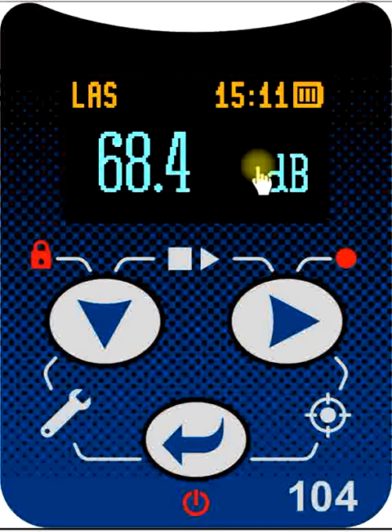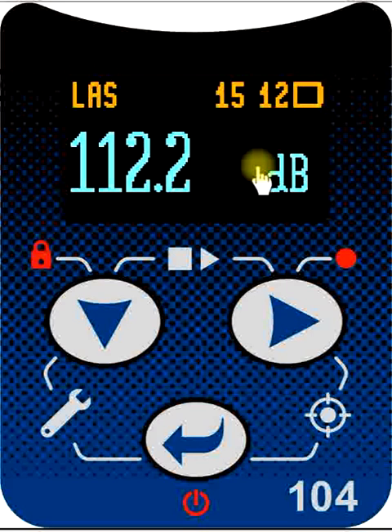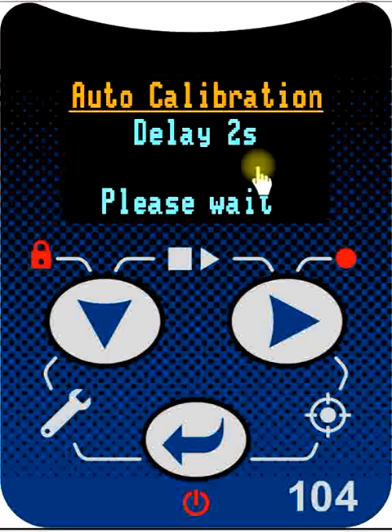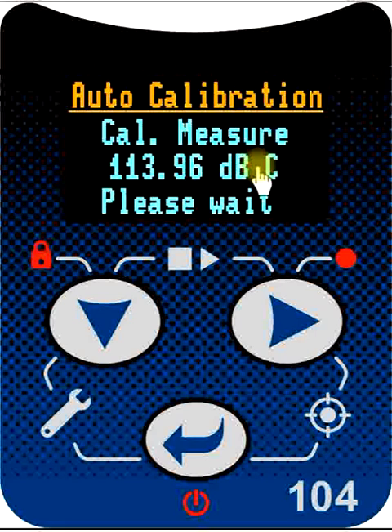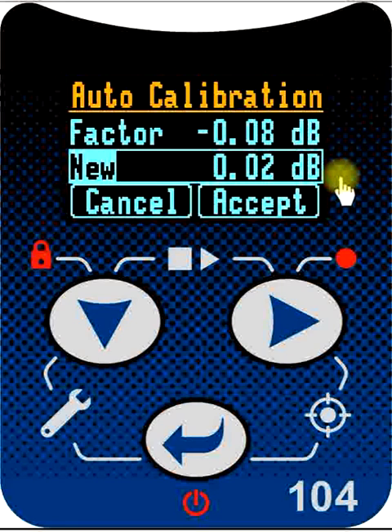So we would get our calibrator, fit it over the microphone, make sure it's a good secure fit, turn the calibrator on, and when the signal stabilizes you'll see that we have the typical 114 or thereabout signal indicated. After a few seconds the instrument goes into the auto calibration routine. It makes the measurement, asks us to wait, and at the end of the measurement gives us the calibration factor that it has had to introduce to bring the instrument into correct calibration.